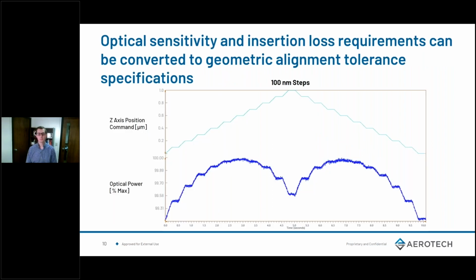The first thing you need to quantify is your optical sensitivity as an alignment tolerance. There are 2 ways to do this. You could physically measure it, which I'll talk about here, or you can simulate it and come up with a number, typically in a tool like Optics Studio. In this case, this particular customer provided me with their optics, and we did this physical test, the results of which I'm showing here. They also simulated it at the same time and came up with a verifying set of data that verified our tests.